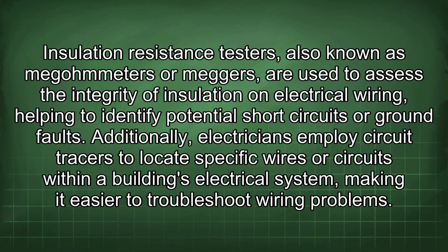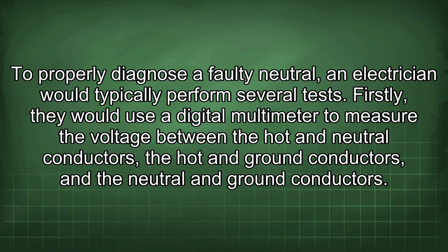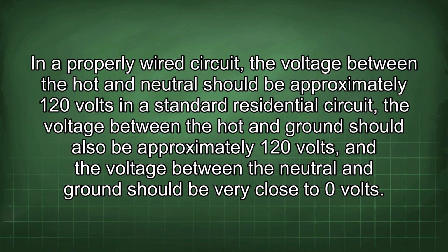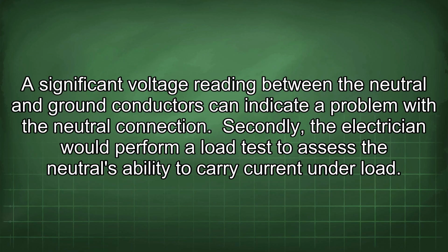troubleshoot wiring problems. To properly diagnose a faulty neutral, an electrician would typically perform several tests. Firstly, they would use a digital multimeter to measure the voltage between the hot and neutral conductors, the hot and ground conductors, and the neutral and ground conductors. In a properly wired circuit, the voltage between the hot and neutral should be approximately 120 volts. In a standard residential circuit, the voltage between the hot and ground should also be approximately 120 volts, and the voltage between the neutral and ground should be very close to 0 volts. A significant voltage reading between the neutral and ground conductors can indicate a problem with the neutral connection.